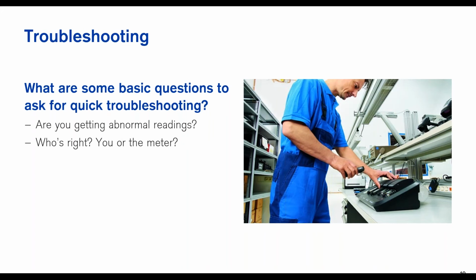Get out, make sure you're in a safe space. Get a second meter if you have one, or something of some other kind of metering technology. So if I'm using a combustible gas indicator meter sensor, then maybe I want to go out and get a Dräger tube that'll measure more or less by mechanical means rather than electronic. Get some other kind of way of verifying that, rather than just saying, oh, it's the meter's fault, that's wrong, and I need to go back in. So always assume the meter is right.